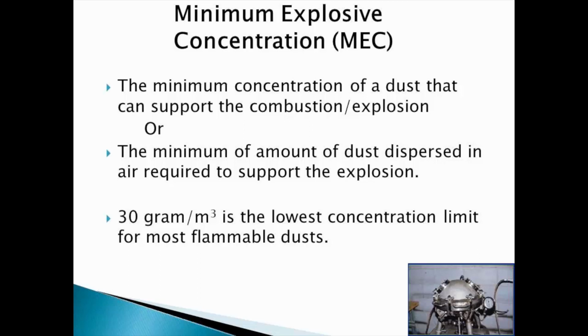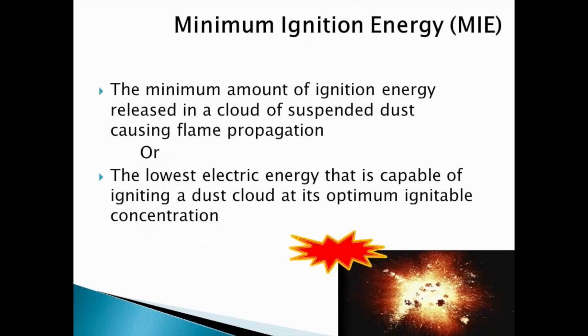For most flammable dusts, the lowest concentration limit is 30 gram per cubic meter. The MEC value can be used as an explosion prevention method in areas where the explosive concentration of dust can be reliably controlled. Minimum ignition energy, or MIE.